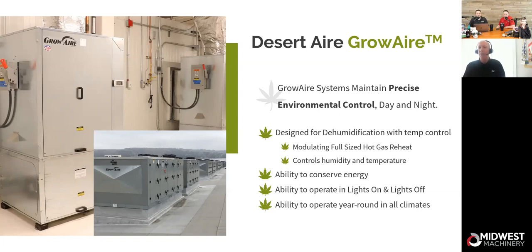So my units run based on whether there's a need for temperature, or they run based on whether there's a need for dehumidification. We have this thing called a modulating hot gas reheat coil, and it's full-sized, and that allows us to rewarm the air that we've cooled in order to remove the moisture out of the air. We get to rewarm that air for free. It's energy we've already spent. We're not having to fire up an electric heater or a gas furnace to bring the temperature back up after cooling it down to remove moisture. So again, another energy efficient method. So that's what we're doing.